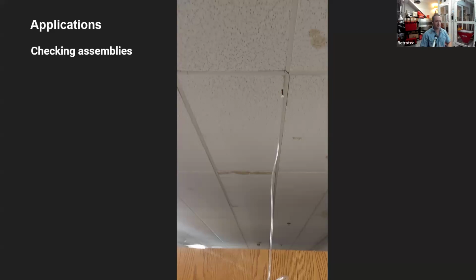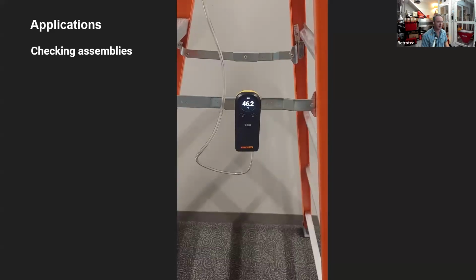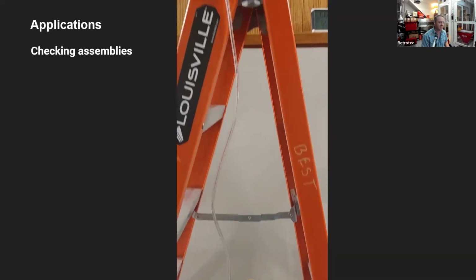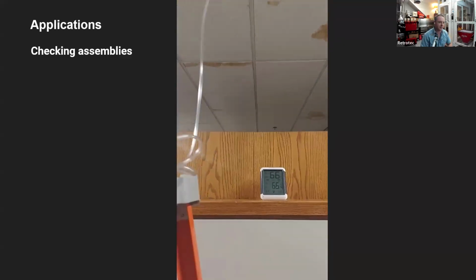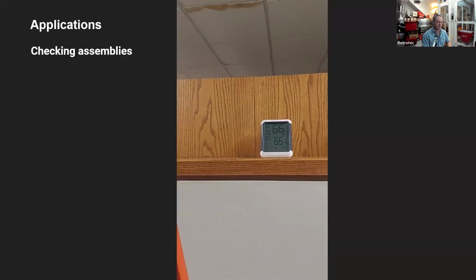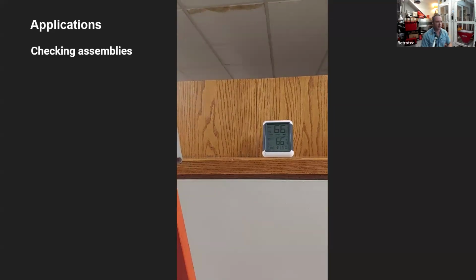As we ran the blower door test, we wanted to see what that space was doing to determine if we could really call it an air barrier. The answer was no. We were running a commercial multi-point blower door test, ramped up to 60 pascals, and were getting about 46 pascals in that cavity. So the space above where the firemen were sleeping is essentially outside, and those ceiling tiles were acting more like an air barrier than the actual barrier above them.